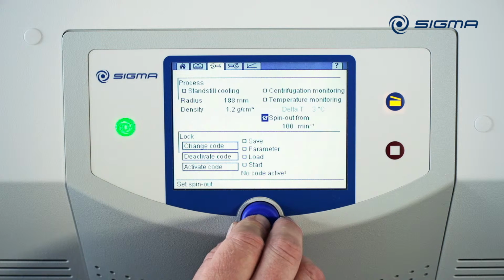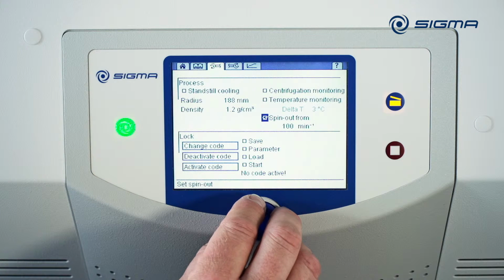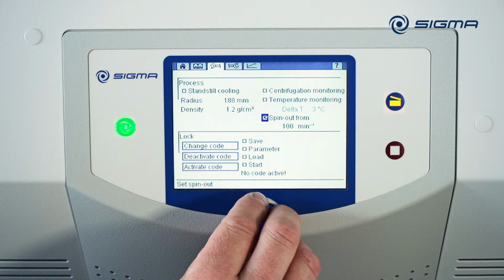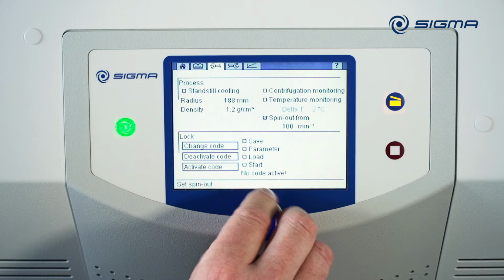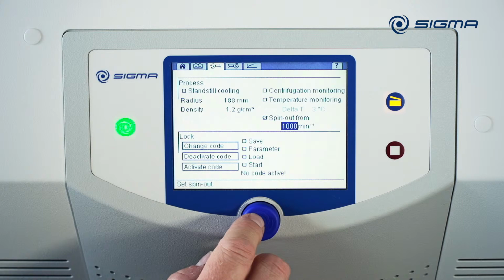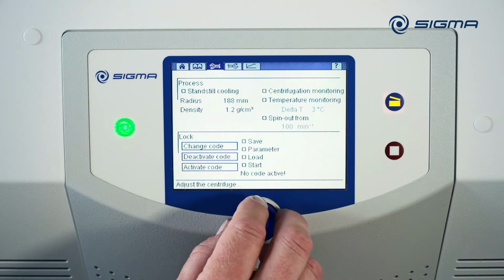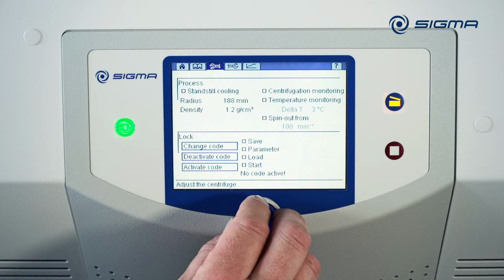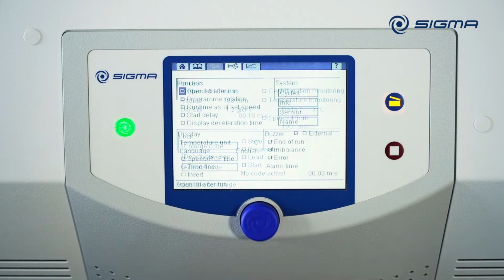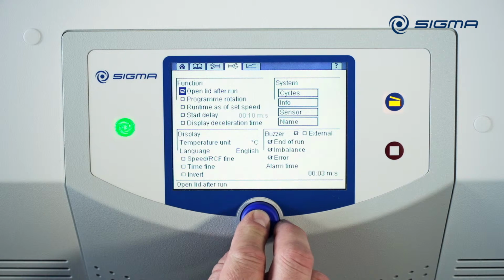If the spin out option is enabled, braking is switched off when the rotor speed reaches a defined value during deceleration. The centrifuge then spins down freely. This speed value can be set anywhere from 100 to 1000 RPM. Under Lock, you can protect saved programs with a password number. This prevents unintentional or unauthorized changes. If the Open Lid After Run option is enabled, the lid lock is released at the end of the run. You should bear in mind that the refrigeration stops running when the lid is open.